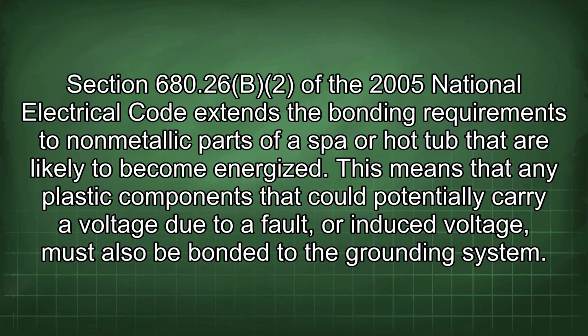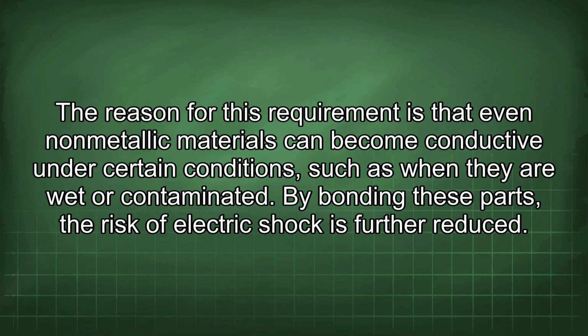Section 680.26(B)(2) of the 2005 National Electrical Code extends the bonding requirements to non-metallic parts of a spa or hot tub that are likely to become energized. This means that any plastic components that could potentially carry a voltage due to a fault or induced voltage must also be bonded to the grounding system. The reason for this requirement is that even non-metallic materials can become conductive under certain conditions, such as when they are wet or contaminated. By bonding these parts, the risk of electric shock is further reduced.